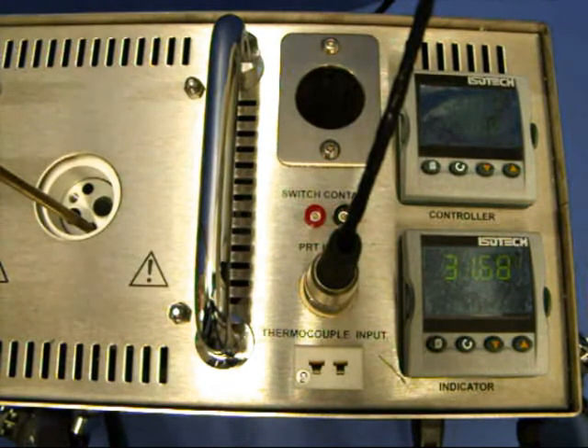Instrument address. Like the controller the indicator has a configurable address which is used for PC communications. Each instrument has an address. This allows several instruments to be connected in parallel on the same communications bus. The default value is 2. The controller defaults to 1. This address would only need to be changed if more than one dry block is connected to the same PC port.